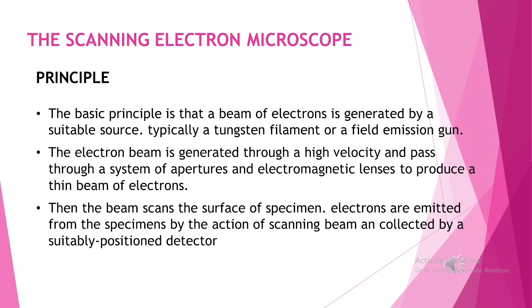First, we are going to look at the principle of a scanning electron microscope. The scanning electron microscope is an instrument that produces a largely magnified image by using electrons instead of light. A beam of electrons is produced at the top of the microscope by an electron gun. The electron beam follows a vertical path through the microscope, which is held within a vacuum. The beam travels through electromagnetic fields and lenses which focus the beam down towards the sample. Once the beam hits the sample, electrons and X-rays are ejected from the sample.